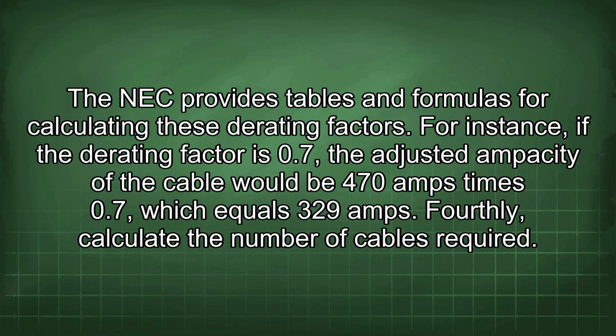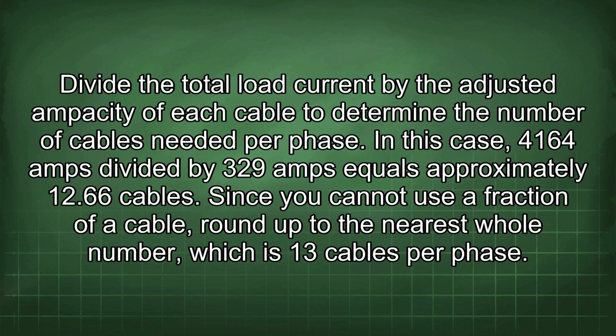which equals 329 amps. Fourthly, calculate the number of cables required. Divide the total load current by the adjusted ampacity of each cable to determine the number of cables needed per phase. In this case, 4,164 amps divided by 329 amps equals approximately 12.66 cables. Since you cannot use a fraction of a cable, round up to the nearest whole number, which is 13 cables per phase.